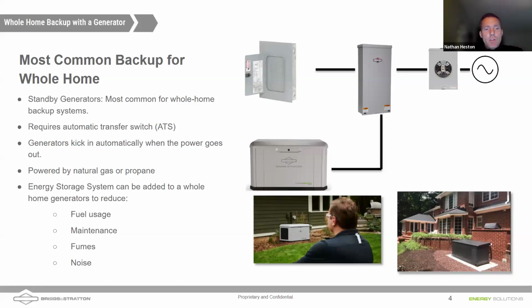And there are some advantages to generators in that you have long duration run times. Typically, you might have a municipal natural gas supply. So Briggs & Stratton makes gaseous generators. We make generators where the engines run off of propane and natural gas. We don't make diesel generators.